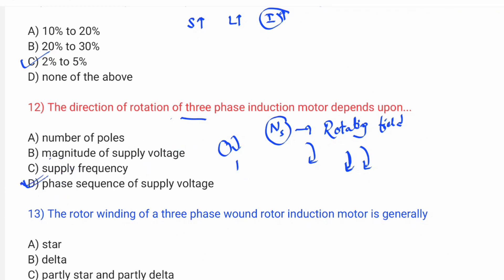For example, if the phase sequence is R-Y-B, the motor rotates clockwise. If you change one phase — making it R-B-Y — the phase sequence changes and the motor rotates anti-clockwise. When the phase sequence changes, the stator field flux direction changes, and therefore the rotor direction changes. Option D is the right answer.